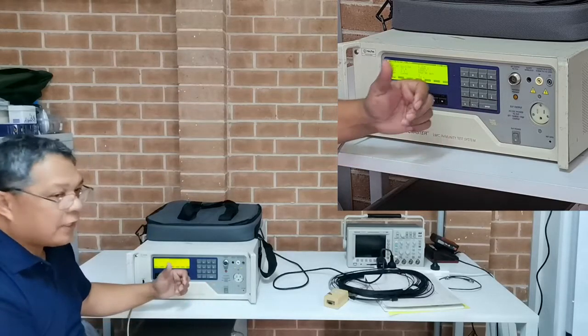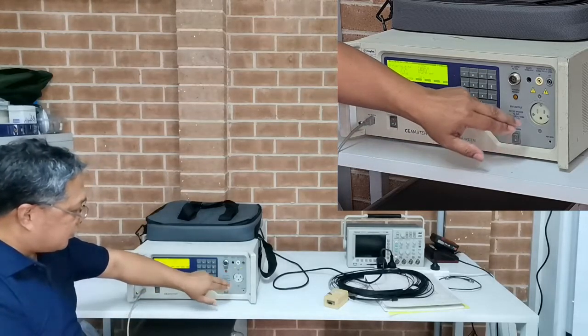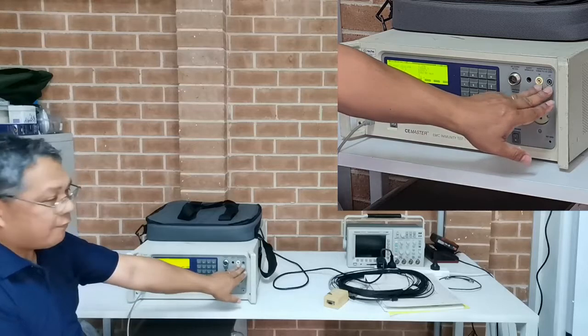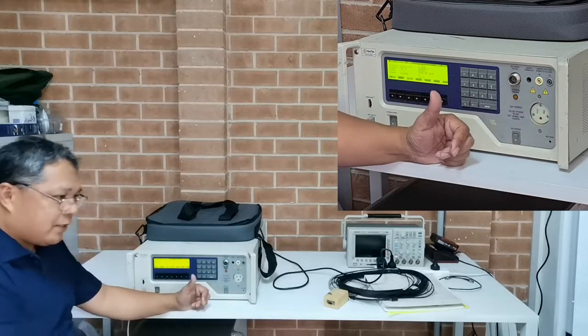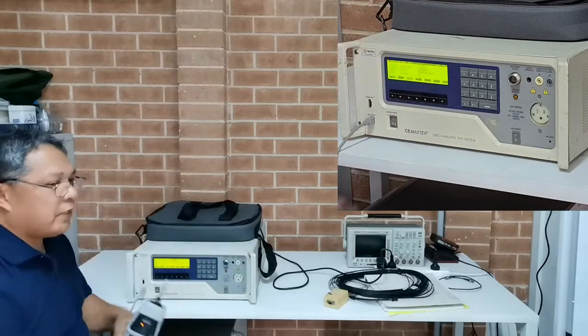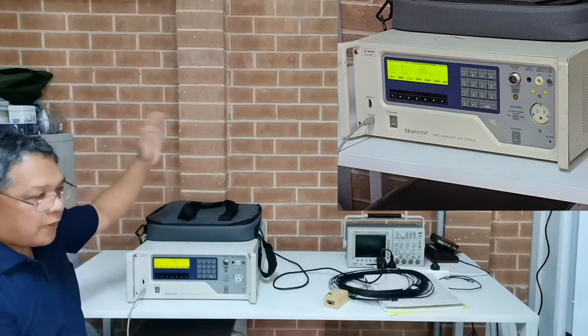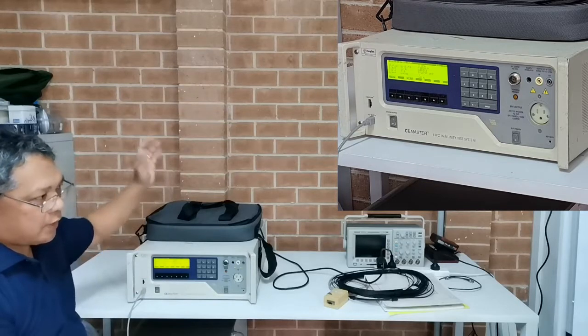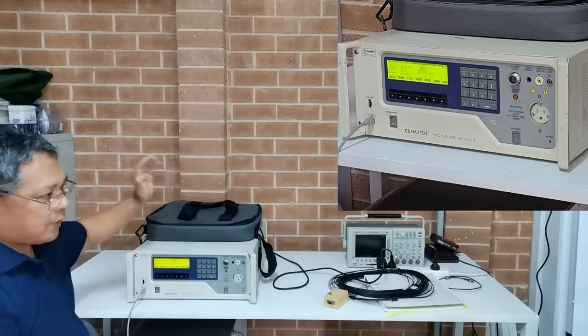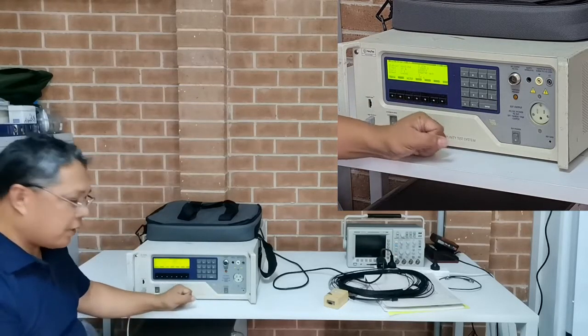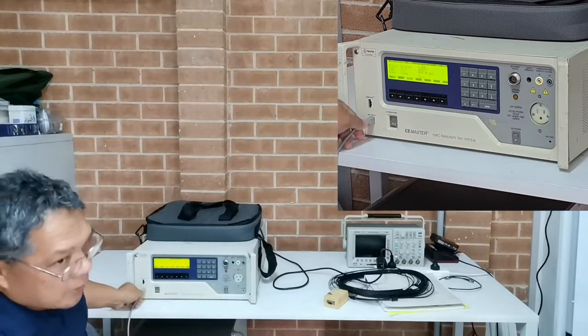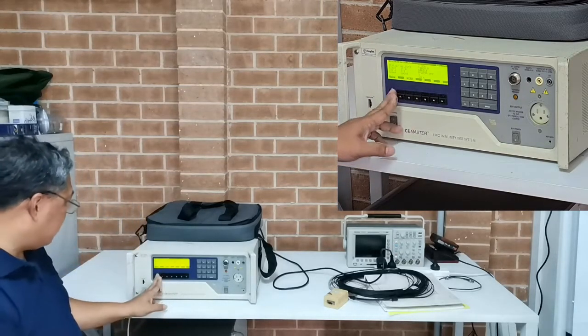And I'll get a differential probe to check whether we definitely have the high voltage here, and we also need to verify that our waveform is within the specs of 1.2 microsecond rise time and 50 microseconds from half to half, as per the new standard 61000-4-5.